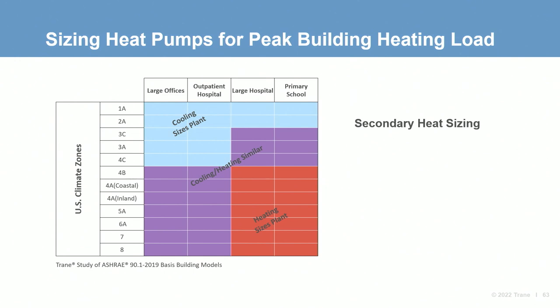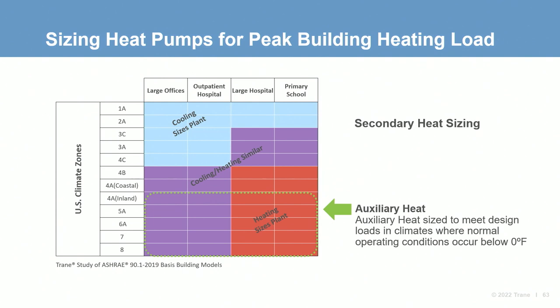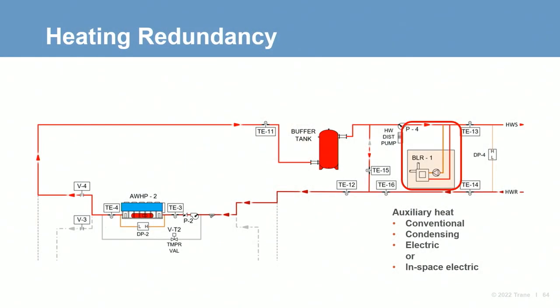For climate zones 4 and some cities in climate zones 3A, emergency backup heat is needed to enable heating during the 20 or 50 year expected extreme. Emergency heat does not need to be sized for design load, but should be sized to protect the building. Design choices for heating redundancy include auxiliary boilers or N+1 heat pumps. Electric or natural gas boilers represent a reliable, low first cost option. If they're only run occasionally for failure recovery or heat pump unit maintenance, their potential impact on the building's carbon footprint may be minimal.